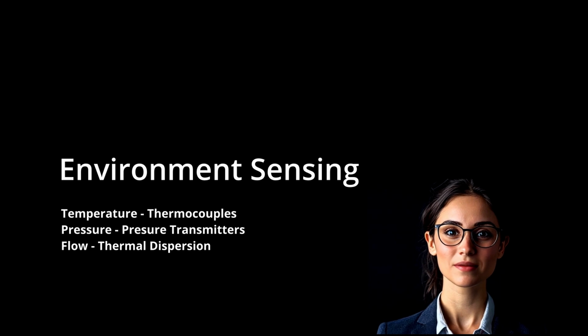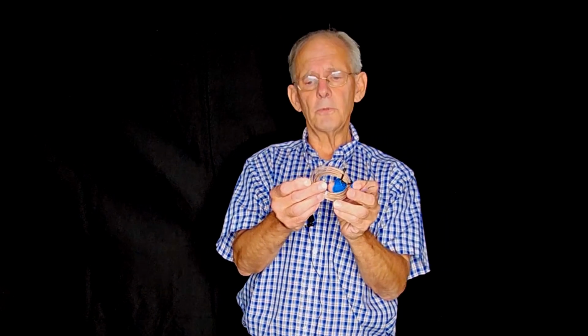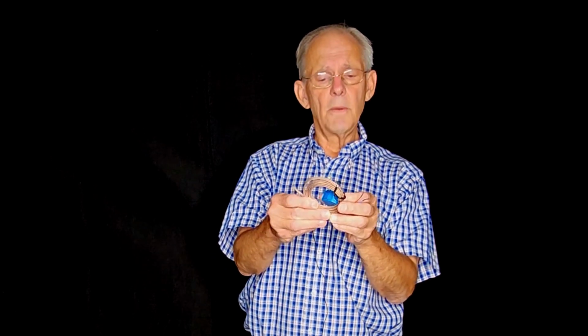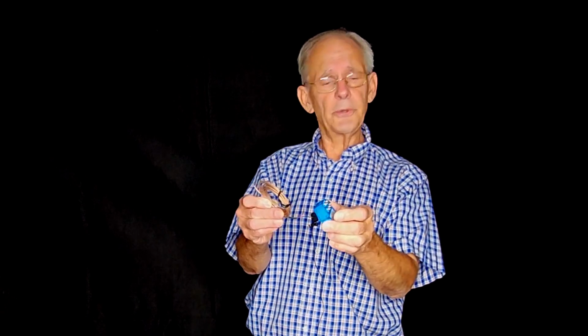Environment sensing. Then we have this guy. This is a transmitter and a sensor. And in this case, the sensor happens to be a thermocouple. What a thermocouple is, is two dissimilar metals that put out a voltage based on the temperature that they're experiencing. And this puts out millivolts, which means that it needs an amplifier to put out the 4 to 20 milliamp signal that we're familiar with. We can also get these in an RTD, resistance temperature device, a type of resistor that changes value with temperature.